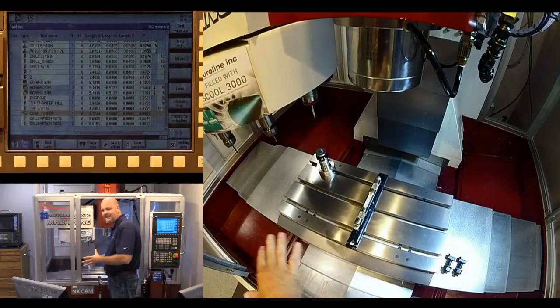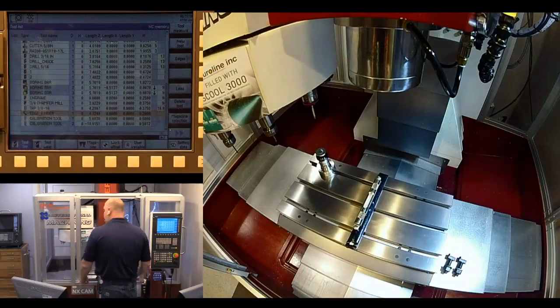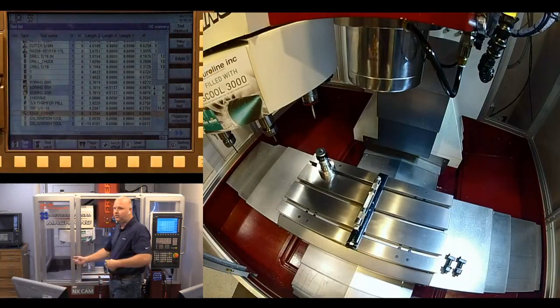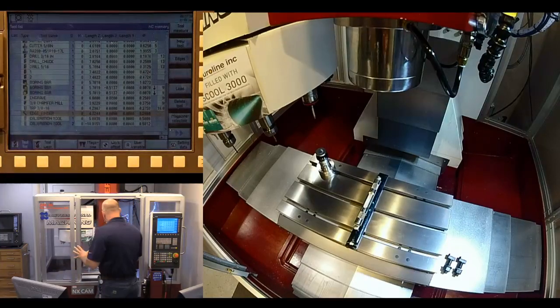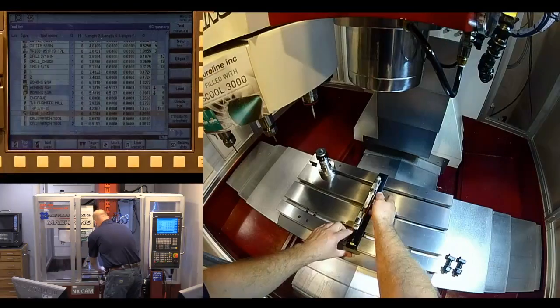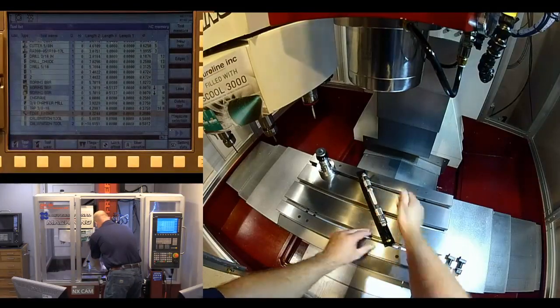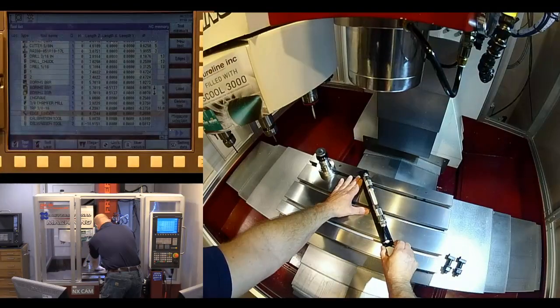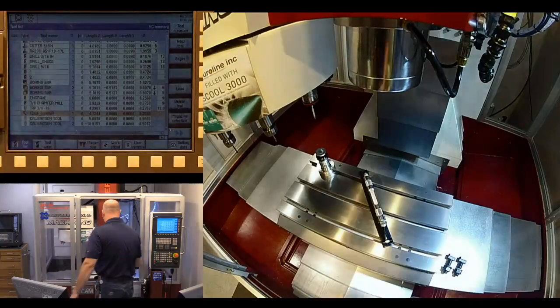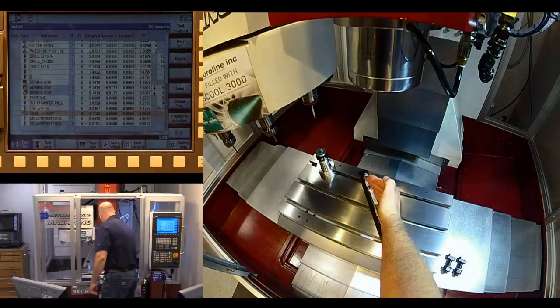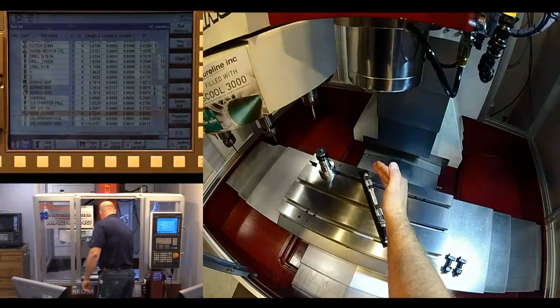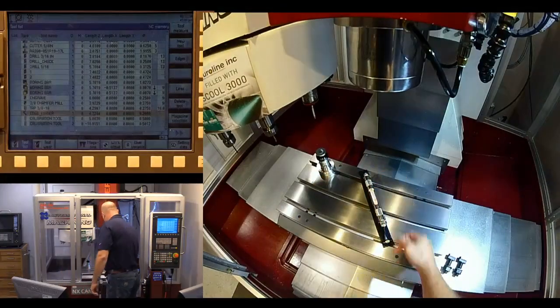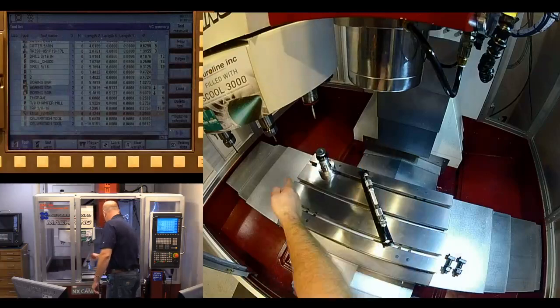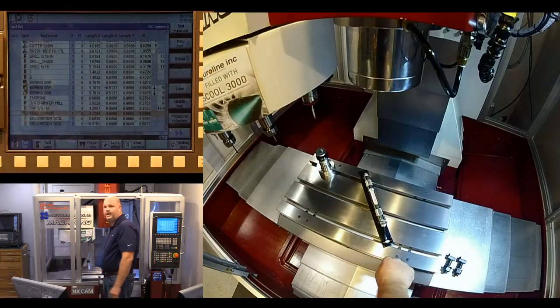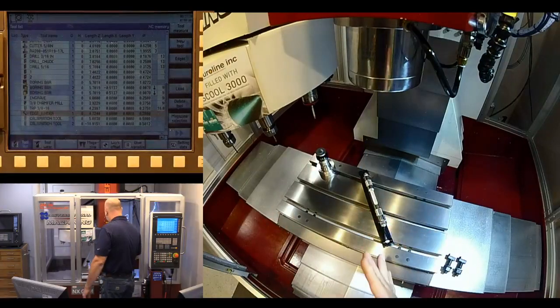Next, I don't want to try adjusting two pads simultaneously, because you're going to be bouncing back and forth and chasing your tail as you move around. So the trick is, you actually want to set your level on your 45s. If I point the level between my two leveling pads, at a 45 degree angle, as I check both measurements, I can isolate to one pad or the other, and determine one specific pad I want to adjust. And then you're going to work it that way.